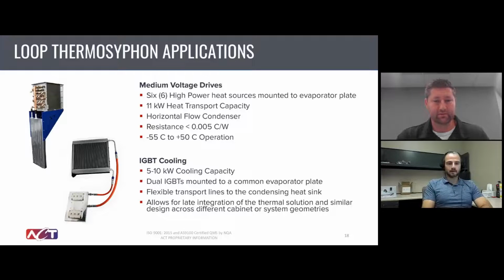I'll just add on that bottom picture there, those orange hoses are high dielectric strength hoses. So for applications where you want to, say, float your modules at the potential of your system and isolate them relative to the condenser, which may be at ground potential, we've demonstrated the ability to stand off 40 plus kilovolts per foot of voltage with this type of solution. So you can get high heat dissipation and maintain isolation between different phases of your system or between an individual phase and ground with a solution like this. Awesome, thank you.